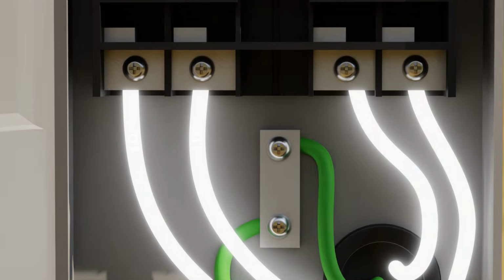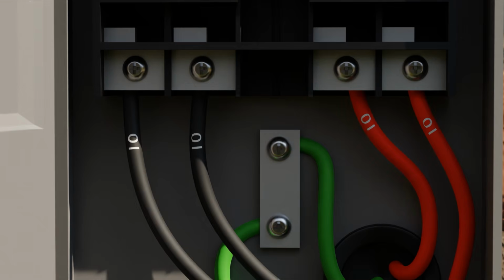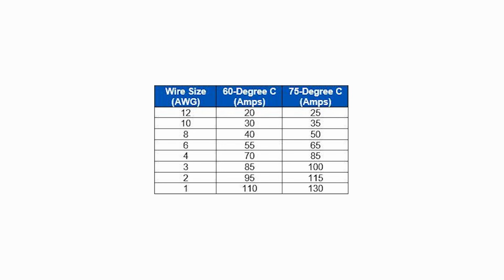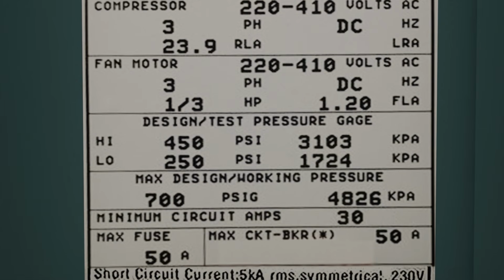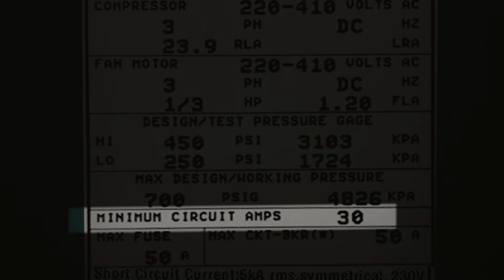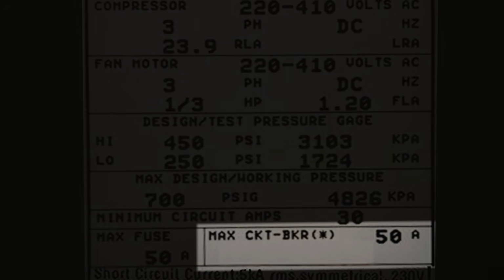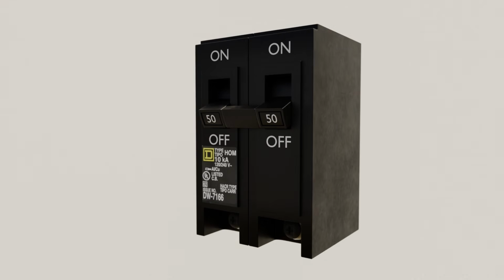Next, confirm your wire sizing. This can be done by referring to a wire sizing table, which is based on NEC Table 310-16. Make sure you have the appropriate wire sizing or larger going into the disconnect and out as required by the data plate. That will be listed as your minimum circuit ampacity. It's also going to list your maximum circuit breaker size on the data plate. Ensure that you have the appropriate circuit breaker that matches the data plate.